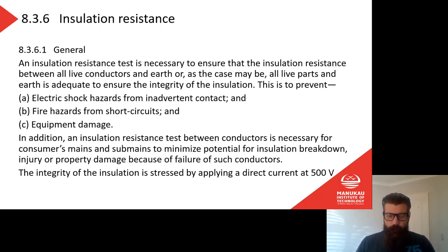One question that people always ask me when they see it, and if you're thinking of this now, you're very clever, is: a 500 volt meter, isn't that dangerous? Would that give me a shock? And the answer is yes it will. Is it dangerous? No, because there's not enough power behind that 500 volts to actually physically hurt us. Will it hurt? Yes. It's like getting a shock from an electric fence. Well, it's much smaller than that. It's like a bad static shock.